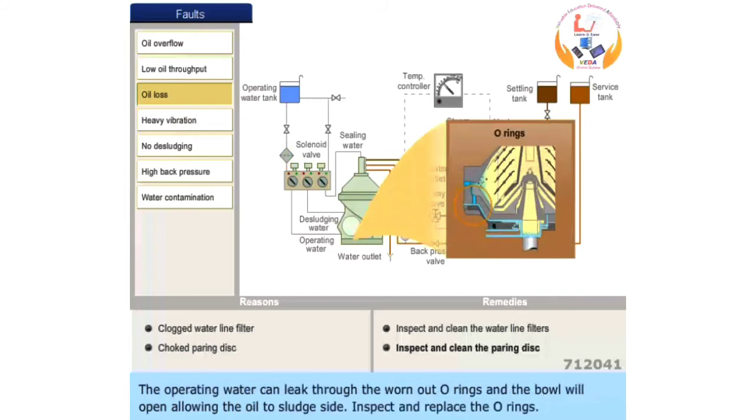The operating water can leak through the worn-out O-rings and the bowl will open, allowing the oil to sludge side. Inspect and replace the O-rings.